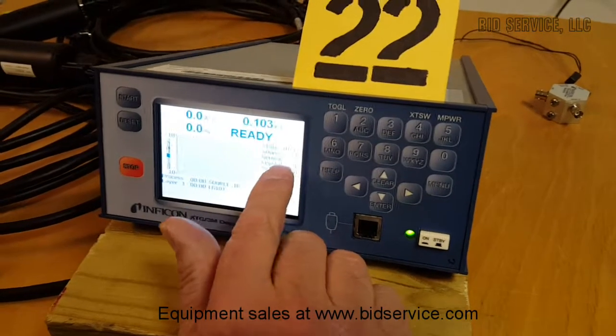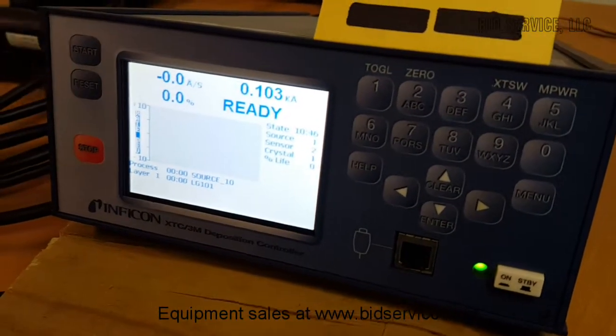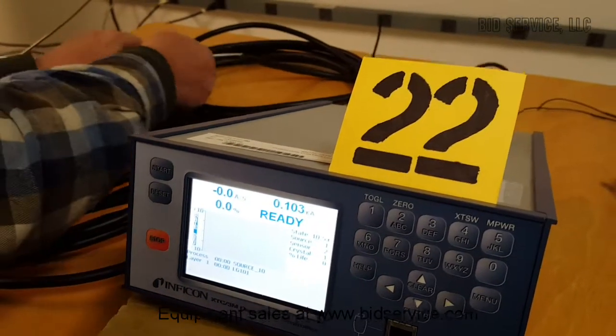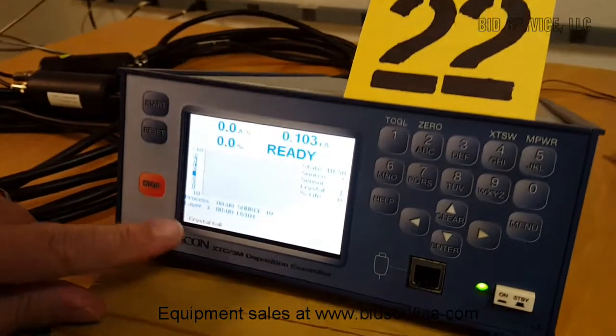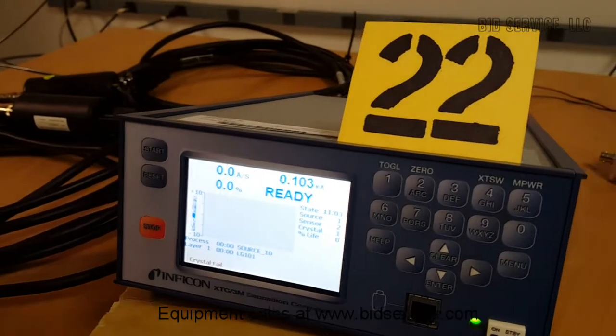You can see our sensor is Sensor 2 — I have this labeled here. I want to show that there's a response, so you can see there are no failures. I'm going to disconnect that crystal interface unit, and as you can see, we now have a crystal failure — so we know that it's responding.